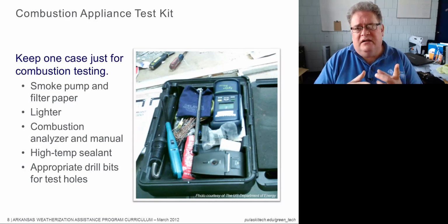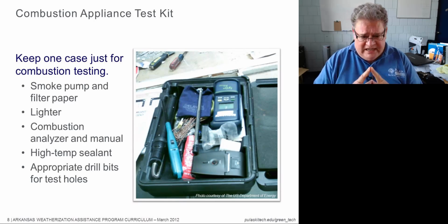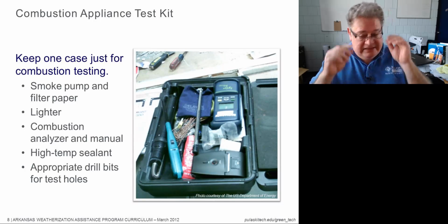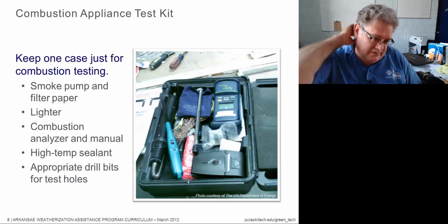If it is higher than that number, at that point you're going to have somebody qualified to tune the equipment up until it passes a smoke pump test. And at that point, then you can put your combustion analyzer in it and see what it's really doing. If you put it in there beforehand, you're risking damaging your combustion analyzer.